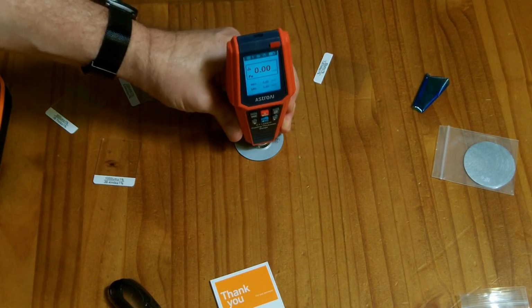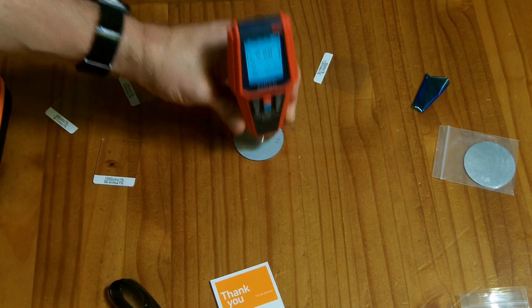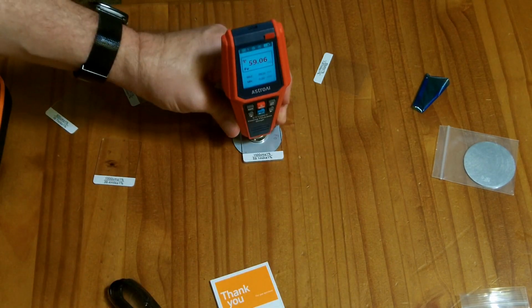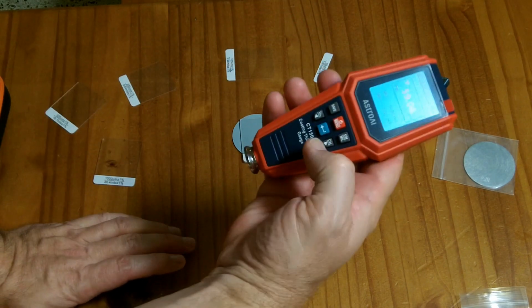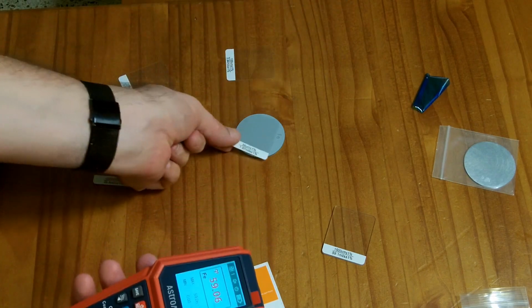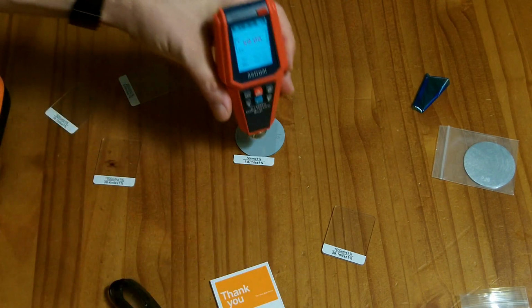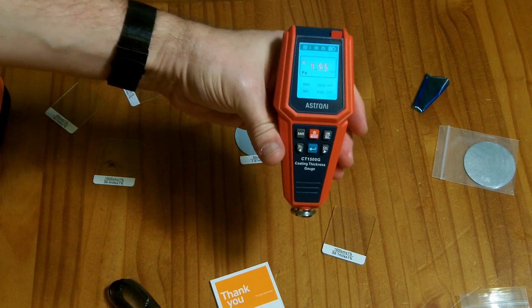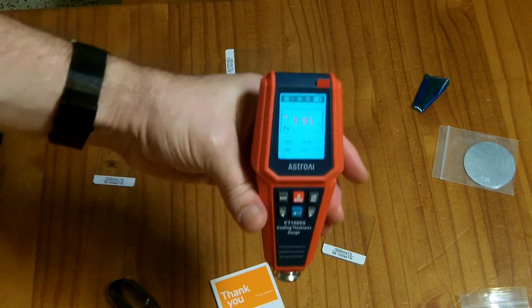Let's try it here. It says zero. That there said 59.06, so that looked pretty good. Here is 1.97 mils. 1.95 mils, so pretty good once you calibrate it.